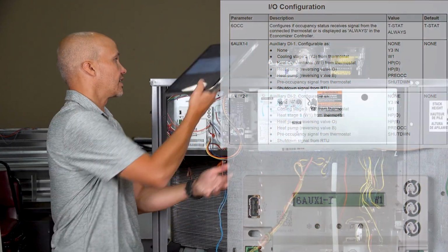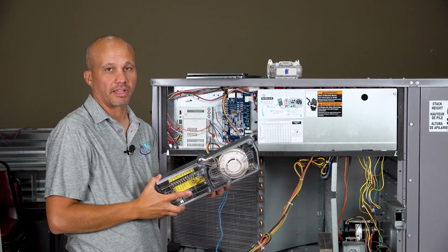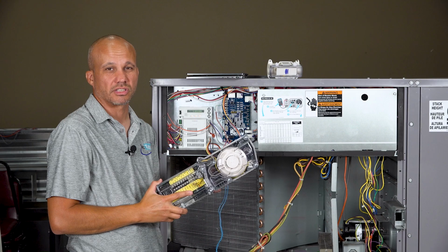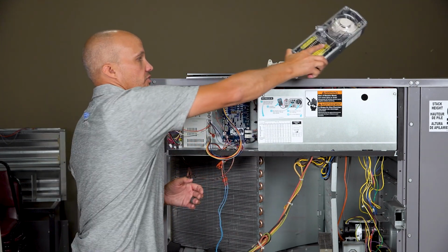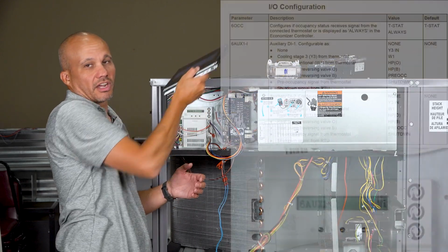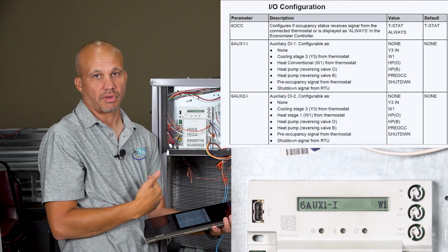You'd use that typically like if you have a duct-mounted smoke detector, which is very frequently required by code as well. Every time you're above 2000 CFM, most codes require you to have a duct-mounted smoke detector. What that'll do is when there's smoke detected in the duct, it'll shut down the fan system, and it'll also close off the Economizer damper.